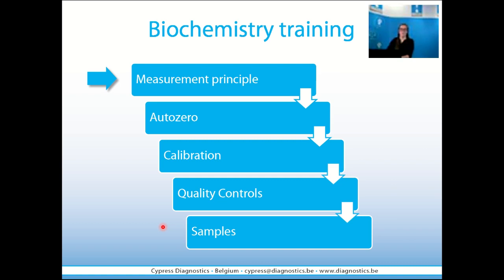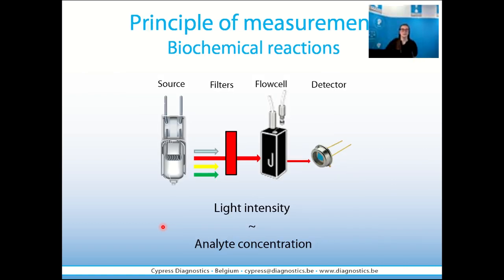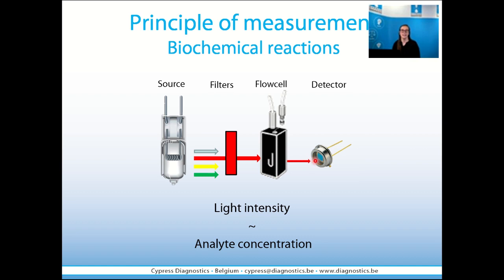The measurement principle. All the Cypress Diagnostics analyzers use the same principle of measurement. A source will emit light which passes through filters with a specific wavelength. This light then goes through the flow cell and it is detected by a detector. The intensity of the light captured by the detector is directly proportional to the analyte concentration. The analyte will be contained in the flow cell.